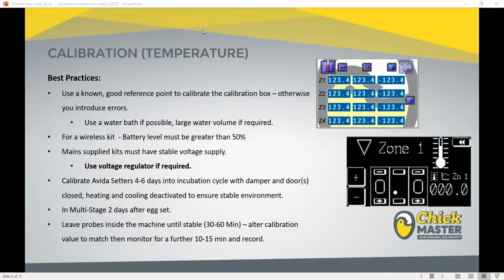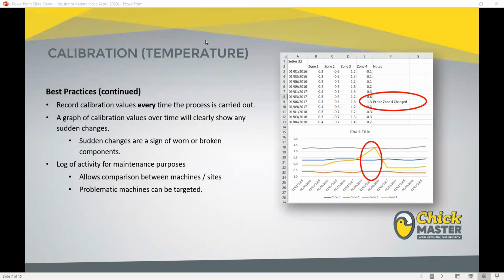Monitor the temperature on your screen and input those values into the HMI or the touchscreen on the front of the machine. The calibration process doesn't stop there. Once you've input those values, you want to monitor them for another 10 to 15 minutes just to ensure that any changes that happen on the probe for the machine are duplicated by the probe on your calibration box as well. So that's a double check, to validate the figure that you've put in. Once you've put the calibrated value into the machine and you've verified it, you want to record those values.